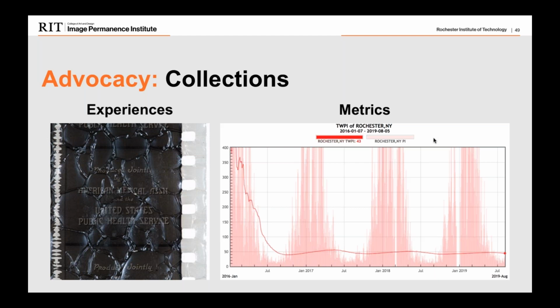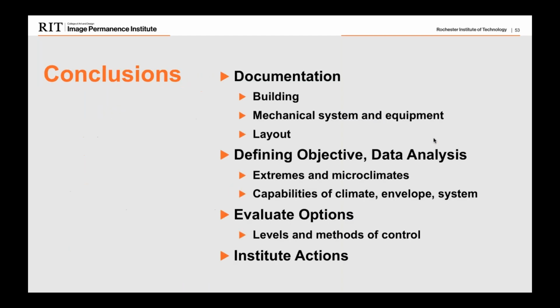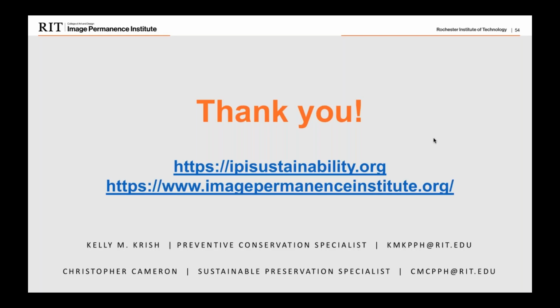One final question: if we were to lower the temperature after hours for an occupied collection space, would you do so only within a 5-degree band? Our main goal with the dead band, when we recommend that, is to set it up so it occurs all day long, fluctuating back and forth, and we want to reduce that as much as possible. What we recommend for reducing the temperature overnight is, instead of running it at say 72 during the day when no staff are present, simply reducing the temperature overall for the space rather than increasing the dead band or giving it more fluctuation.